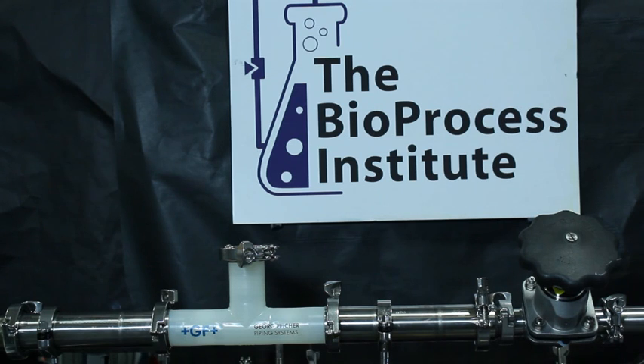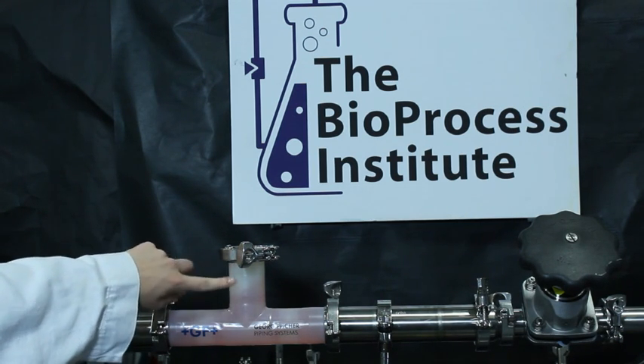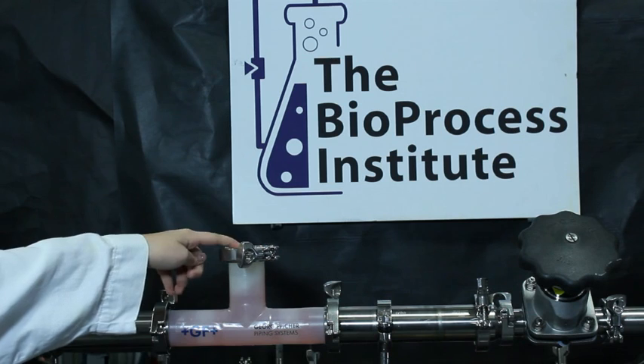Let's turn on the pump and see what happens over the course of a few minutes at a velocity of approximately 5 feet per second. As you can see our air pocket is still remaining so let's give it a minute or two and see what happens to our grape juice.